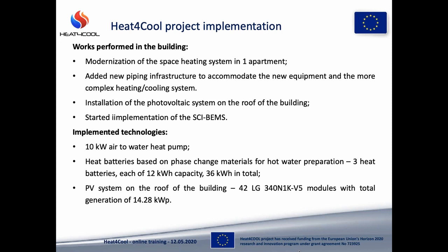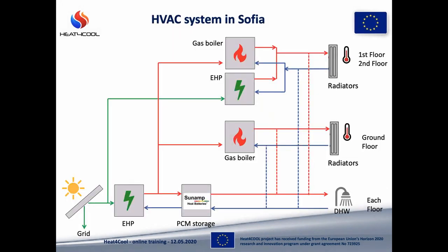The heat pump unit is installed at elevation minus 2.40 meters. The phase change materials, also called heat battery, are installed in the vicinity of the heat pump unit. After the heat pump unit, 2 thermal loops are formed, one to the heat batteries and the other to the heating system. Circulation to the thermal circuit for the thermal batteries will be performed via a circulation pump, indicated as circulation pump 1. Circulation to the heating circuit will be achieved by means of a second circulation pump, which is named circulation pump 2. Only one circulation pump will work at a time.